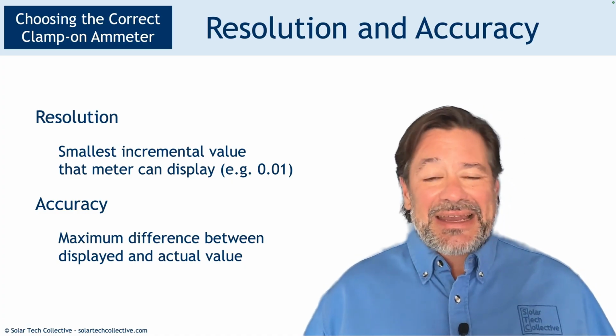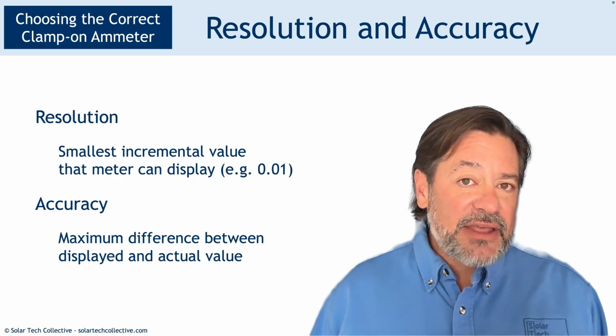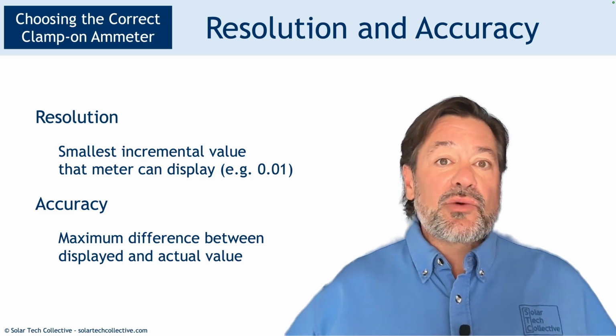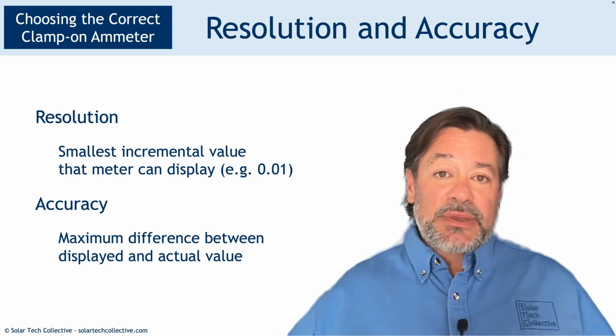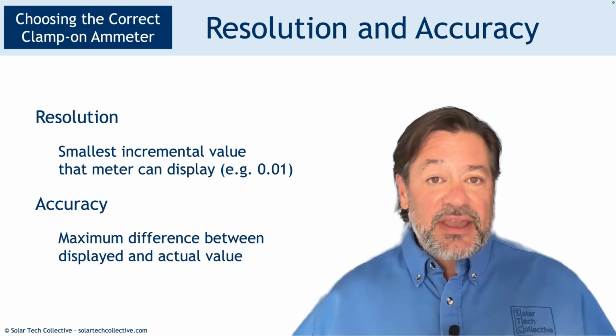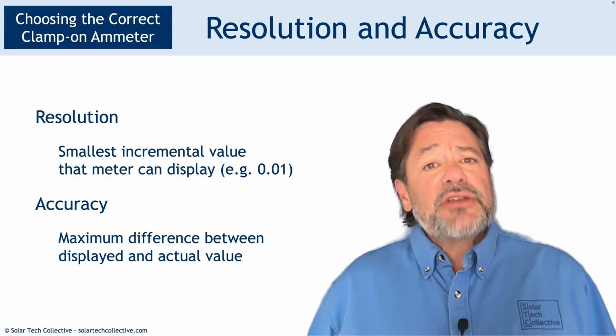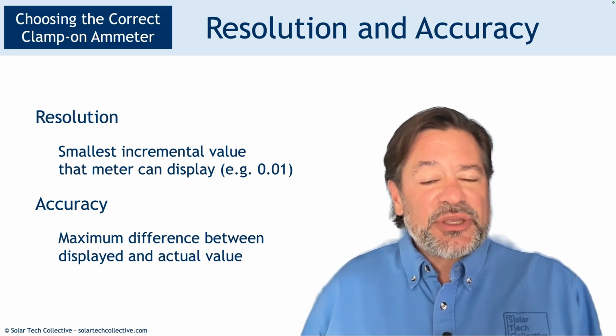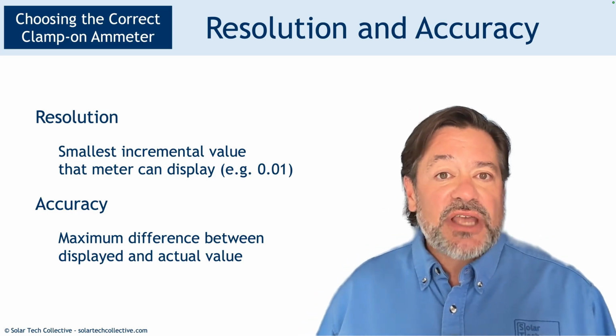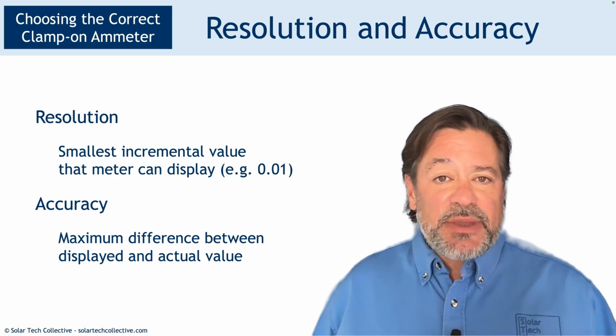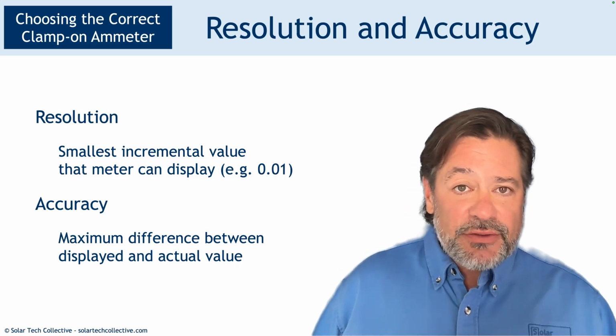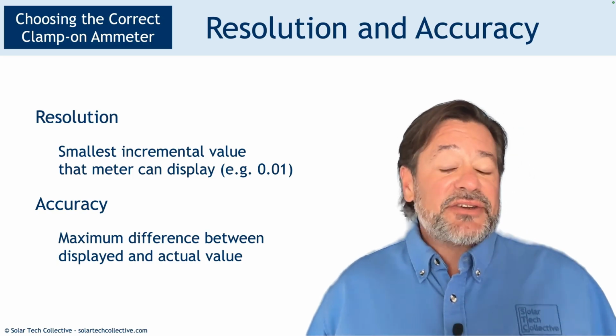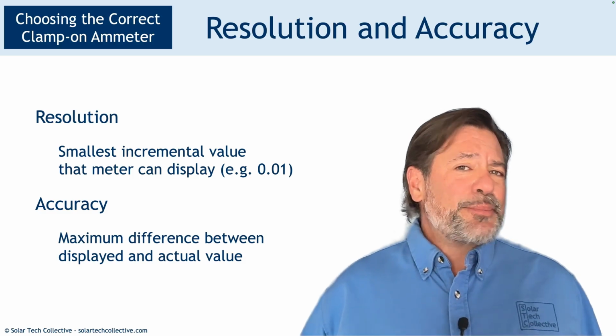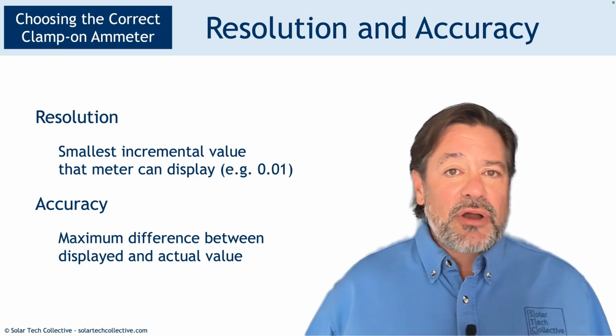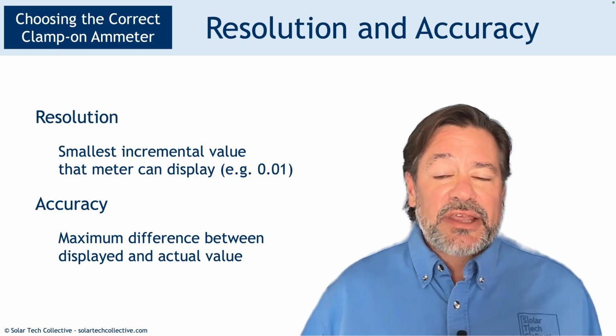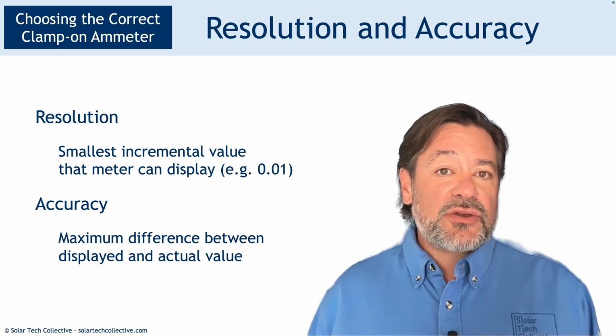Again, a higher quality meter is going to give you better values. You also see that at wider ranges, often the accuracy is going to be less than if we have a lower range. And also, our accuracy will change based on how the clamp is placed around the wires themselves. If you're out on the outer edge, it's going to be a little less accurate. If you're right dead center through the middle of that clamp, it's going to be more accurate. Does it really matter for what you're doing? Probably not. We're always going to have some fluctuations when we're doing our clamp-ons anyway in terms of the current value we read.